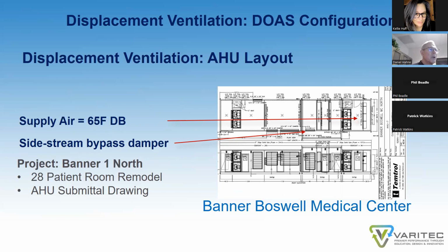There's a damper and a bypass section that modulates open and close to maintain a leaving air temperature out of the air handler, 62, 65 degrees, since the mixed air condition is perhaps about 80 to 85 degrees, certainly in cooling. And then you provide your adequate dehumidification at the cooling coil and then reheat it without using additional energy by mixing that mixed air into that supply airstream.